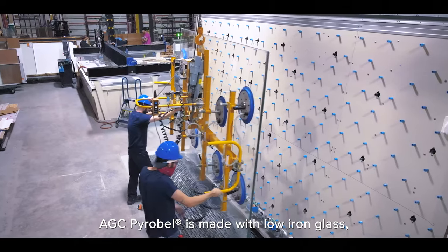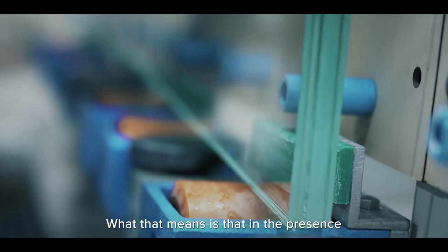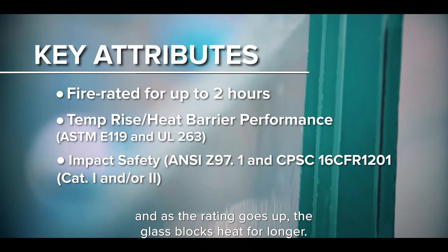Pyrobel is made with a low iron glass, so it is absolutely colorless, and the interlayers are intumescent. What that means is that in the presence of a fire, those interlayers expand, and as the rating goes up, the glass blocks heat for longer.